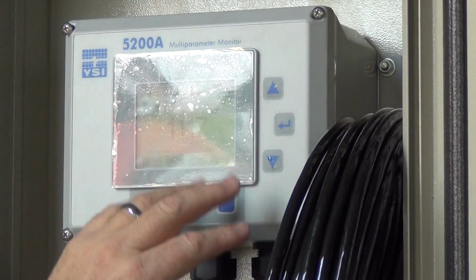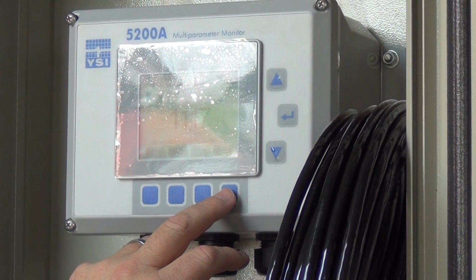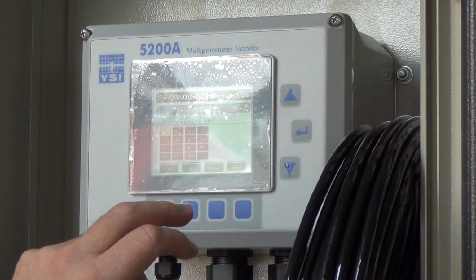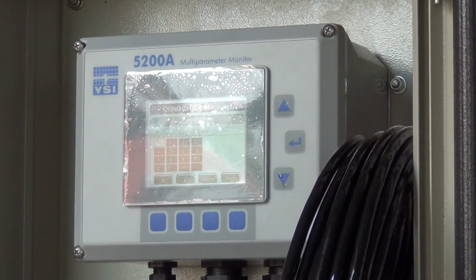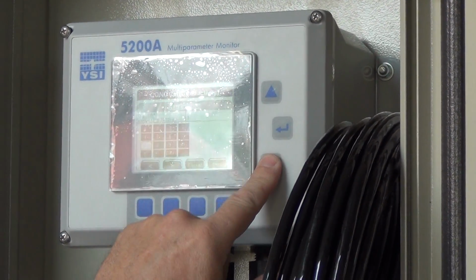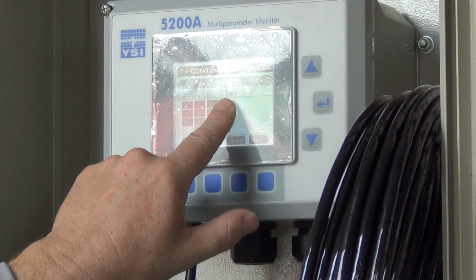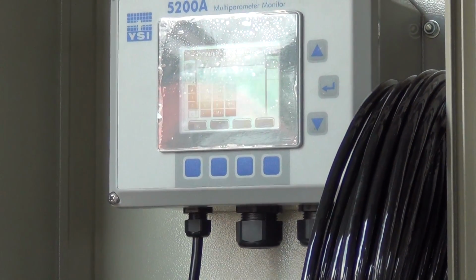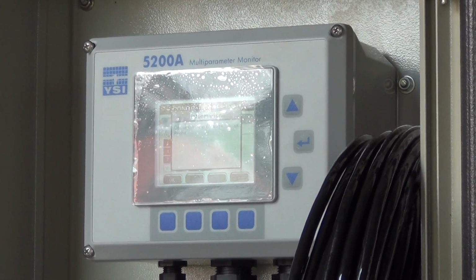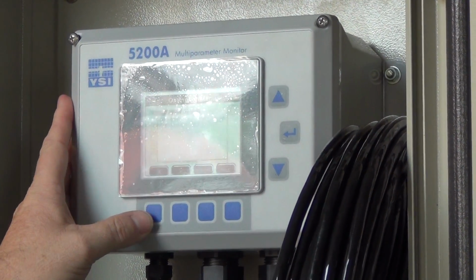So, what we're going to do is, it's stable, not changing. So I'm going to press the next button, and it says, what is the value? The value is 1,000. So I'm going to put in 1, 0, 0, 0. You can see 1,000 right there. And I'm going to press save. Calibration out of range, check probe. Not good. So what I'm going to do is exit out.